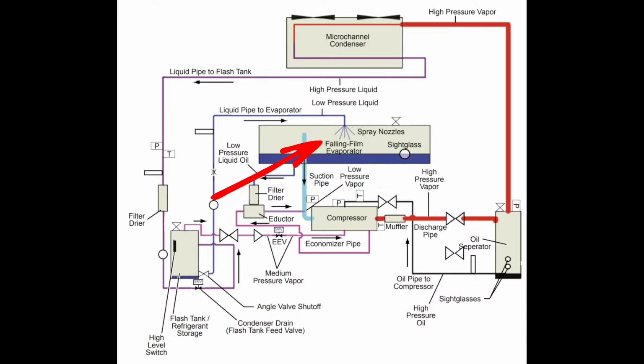And they actually reference the falling film evaporator in the Style A as more of a true falling film. And if I'm not mistaken, one of the ways you know a falling film is how low the liquid level is in the evaporator. On the Style A's, they had the sight glass really far down, really close to the bottom of the barrel. And that's where you tried to maintain liquid levels. About half of that sight glass, 1/3 to 1/2, was kind of the target for these machines.